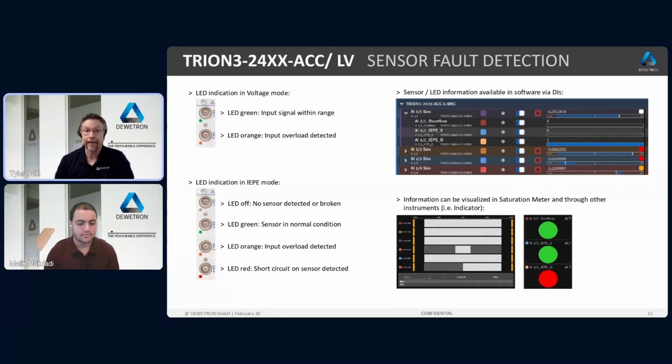Now you can look at either the faceplate on the actual card itself and see if there's any shorts or anything happening with it, or you can look directly in your Oxygen platform, in the software, to see if any of those devices out in the field aren't connected properly, or if there is an issue. Saves you a ton of time, saves you money, and just makes your lives and everybody's lives a lot easier.